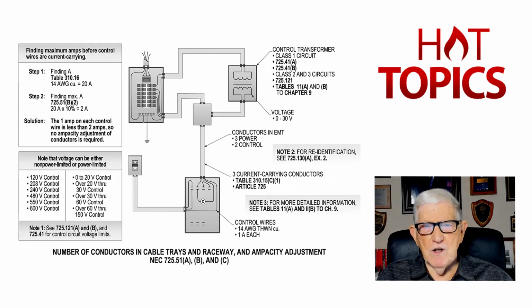Now notice in the illustration, you have 3 power conductors and 2 control circuits. But the number 14 control circuits is only 1 amp, so you haven't exceeded step 2 to the left-hand side of the illustration, where the 2 amps is derived from 10% of 20. So you wouldn't consider them current carrying conductors. Now, you're either looking at 725.41(A) and (B) for class 1 circuits, and those can be harmful to you under certain conditions, so you really want to check them.